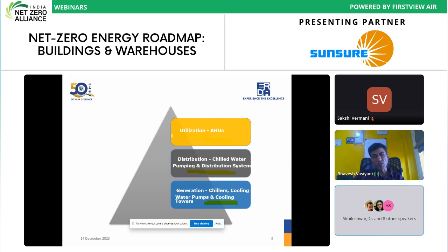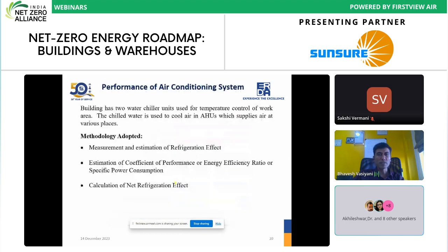Higher supply with lower requirement will make a loss in the system. So in this case, what is happening, we will understand from one case study. This building has two chiller units used for temperature control of some working area, and normally we use AHUs which supply cold air or chilled air to the conditioned area. Air is taking chilling effect from chilled water. Chilled water is coming from the chiller compressor.